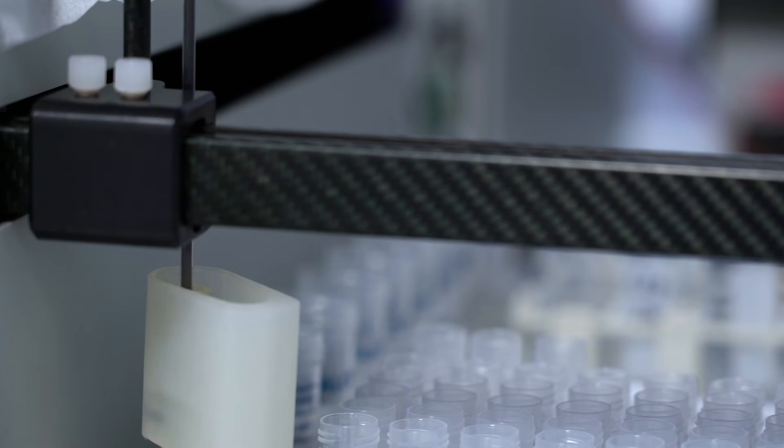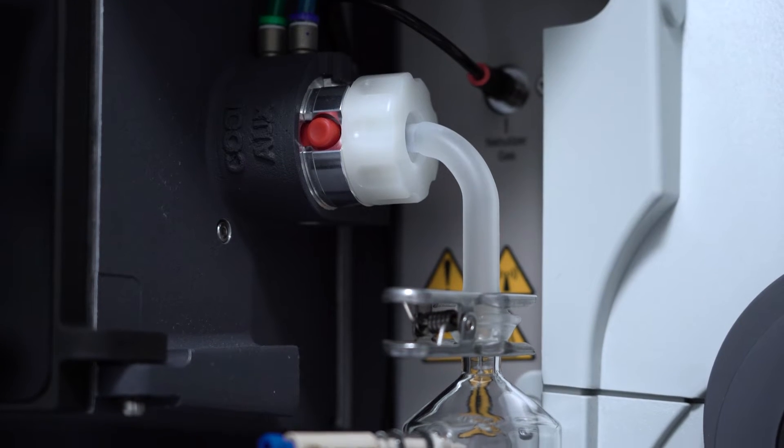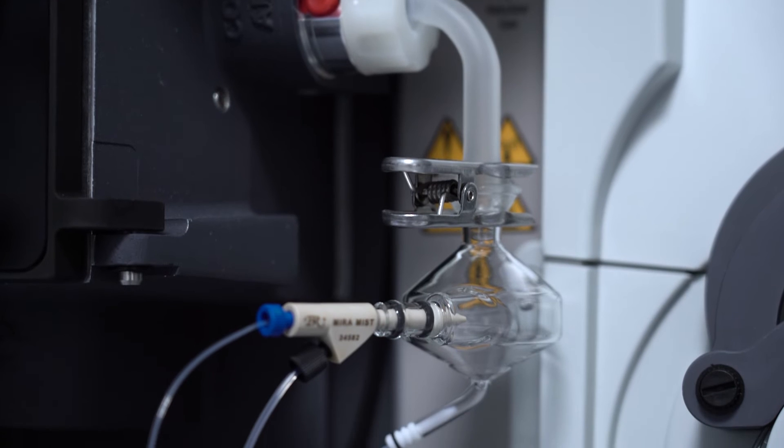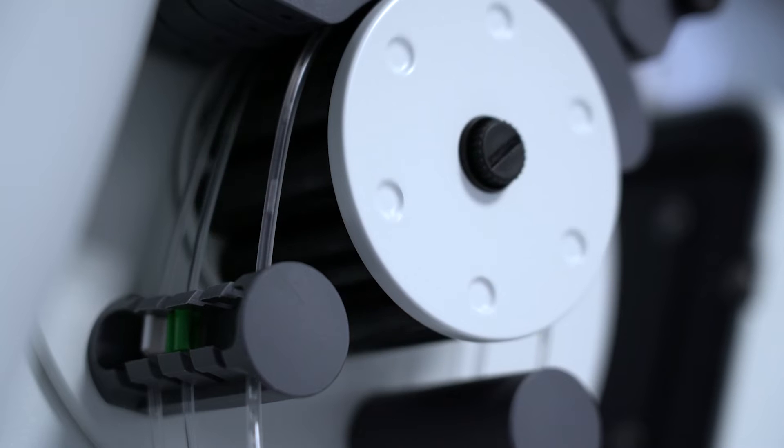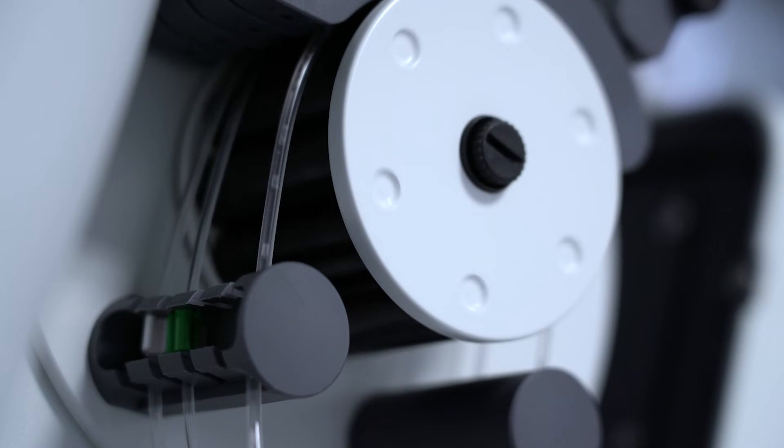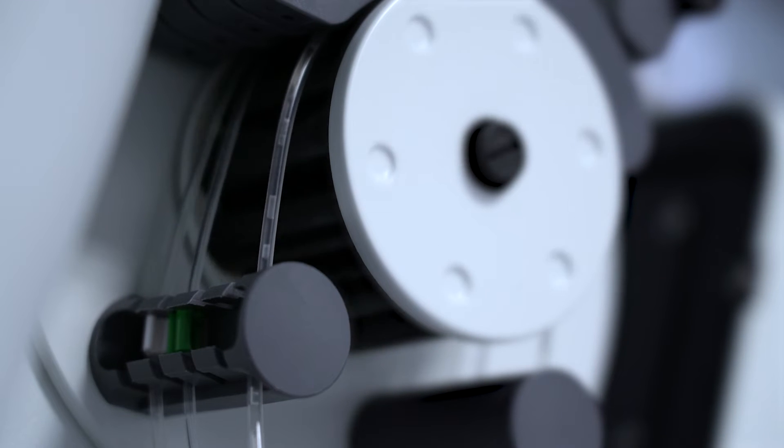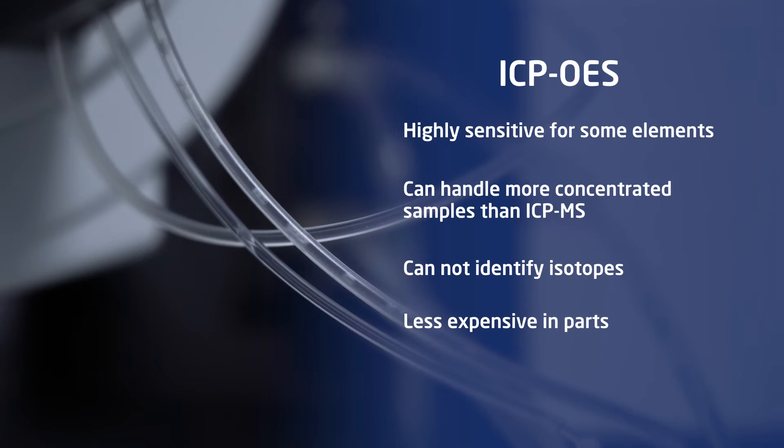The ICP-OES also needs a plasma and a nebulizer, but it measures light emissions instead of ions. It therefore has similar requirements regarding gas and the nebulizer, but needs no high vacuum parts and does not need to discriminate by mass, saving some expensive parts.